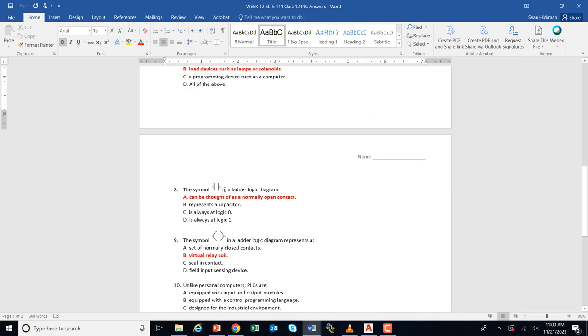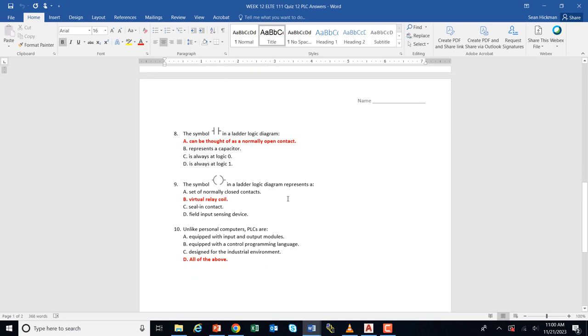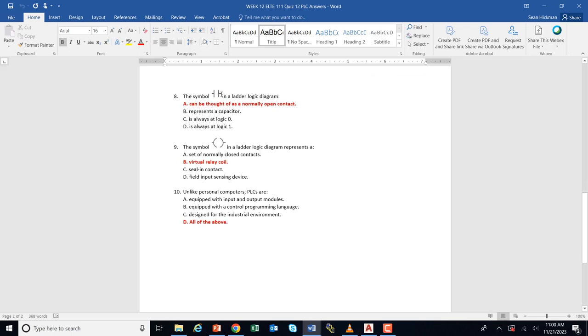A normally open contact symbol in ladder logic is called an XIC — examine if closed — and you program it thinking it's like a normally open contact; it goes from false to true when something happens. The coil symbol in ladder logic represents a virtual relay coil. The PLC is programmed only using contacts and coils — there are no push button or solenoid symbols in ladder logic. Unlike personal computers, PLCs are equipped with input and output modules for wiring, use a control programming language like ladder logic, and are designed for the industrial environment.